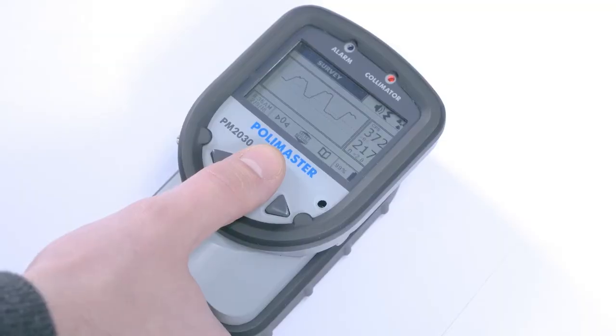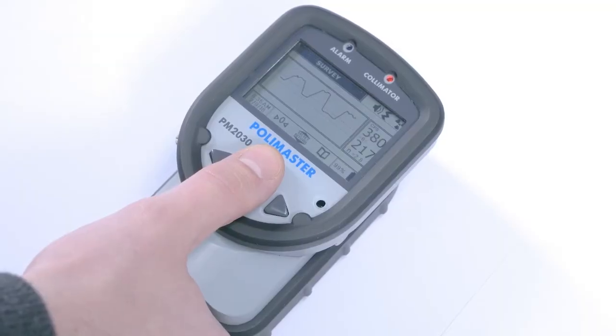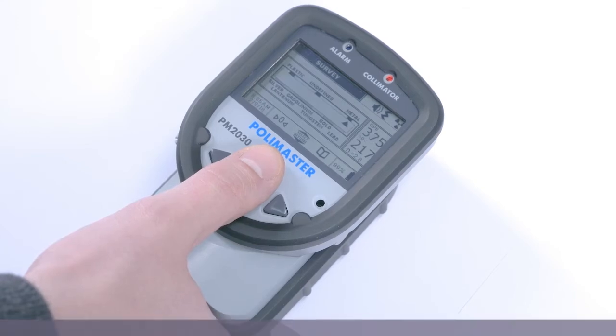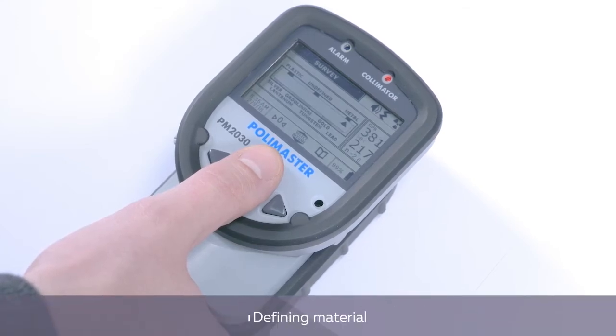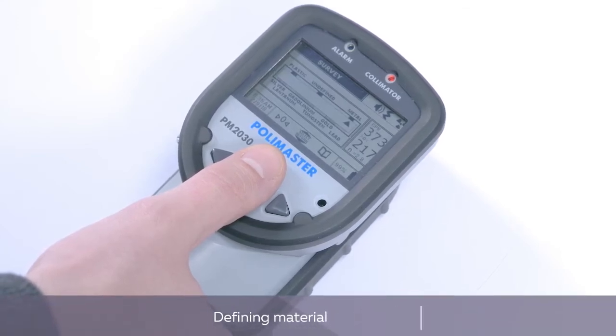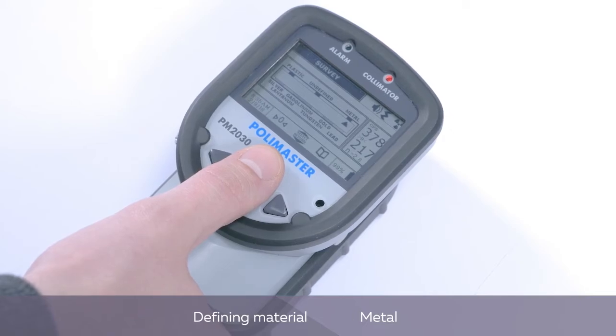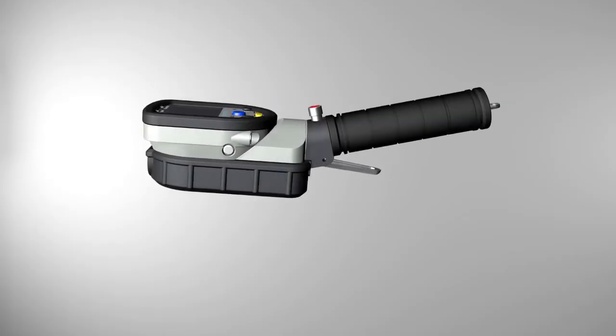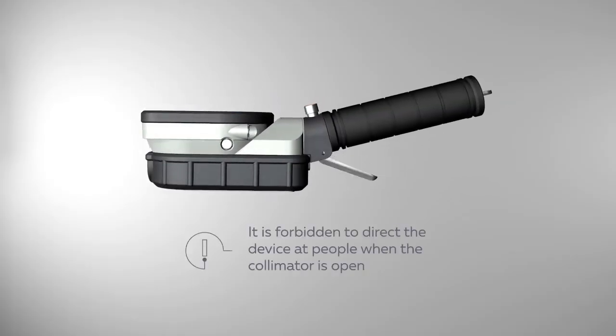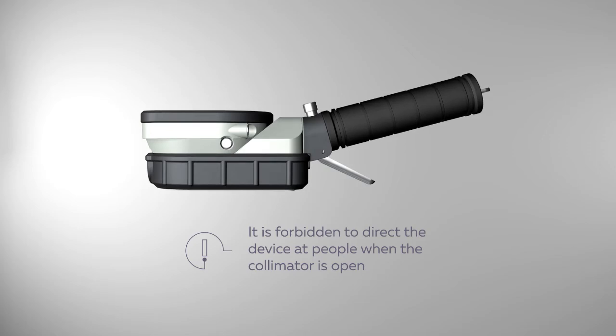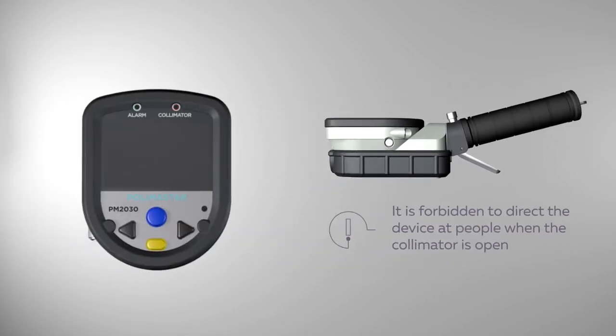At the same time, the frequency of repeated signals can help to identify the size and density of the hidden objects. The material of the insert can also be defined. Select the display form of material indication and wait several seconds. To complete the operation, close the collimator by pressing and releasing the lever. To return to the main menu, press the Return button.